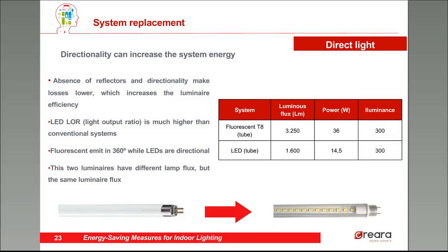And finally, directionality — direct light. Directionality makes LEDs even more efficient. The directionality and also the absence of reflectors increases the luminaire efficiency. The light output ratio is much higher in LEDs than in conventional systems. This table compares a fluorescent lamp and a LED: the fluorescent is more powerful at 36 watts against 14.5 watts, and its flux is higher at 3,250 lumens versus 1,600 lumens. But the directionality means the illuminance is the same in both systems. However, we can't forget the glare problem — directionality can cause glare problems.